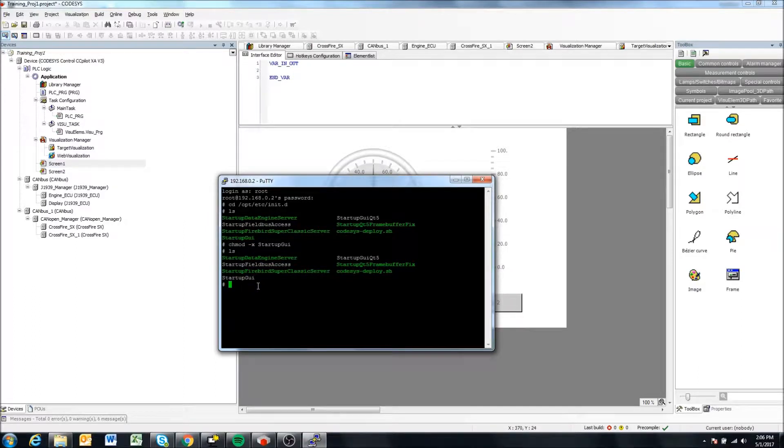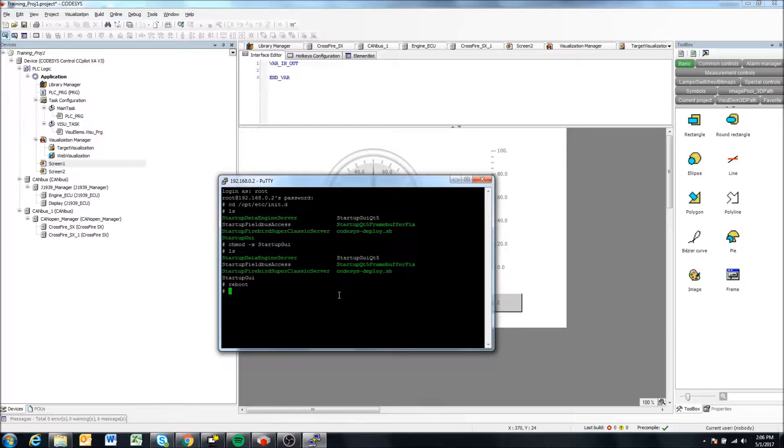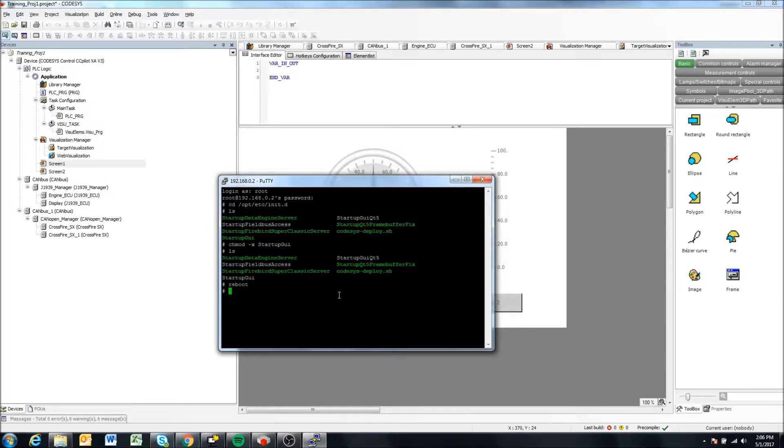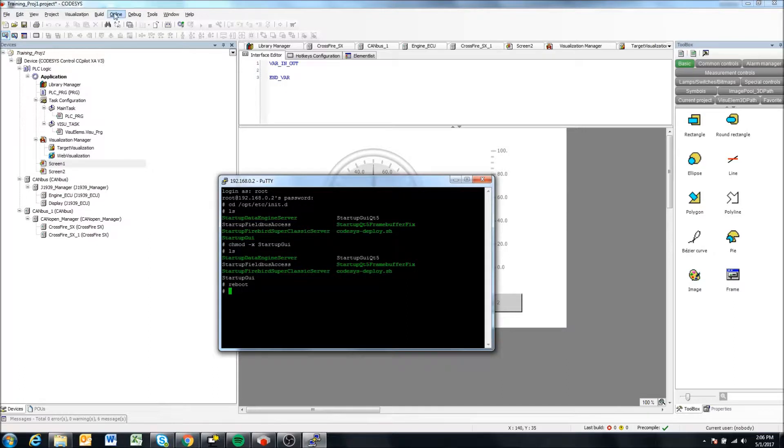So now when we reboot our display, the CODESYS application should boot. But the original startup settings application will not boot. So only the CODESYS application will boot, which is what we want.